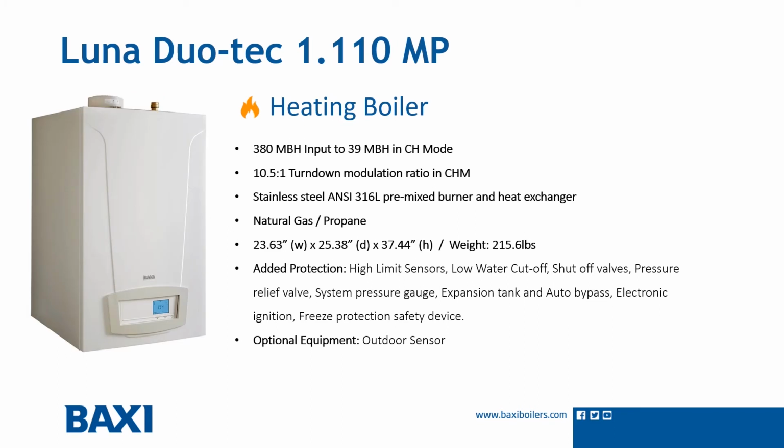The MP 1.110 is our biggest light commercial unit. It has a BTU rating of 380,000 to 39,000 for your central heating needs. This unit also does not have the gas adaptive technology, but is still field convertible from natural to LP with no additional kit required. The MP 1.110 has a turndown ratio of 10.5 to 1. The unit is 23 inches wide by 25 inches deep and 37 inches high and weighs 215 pounds.